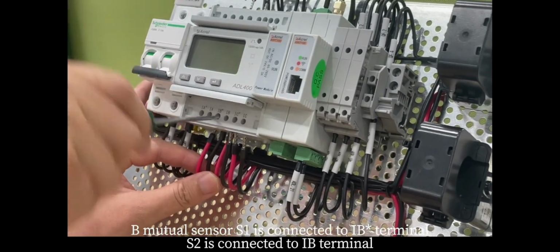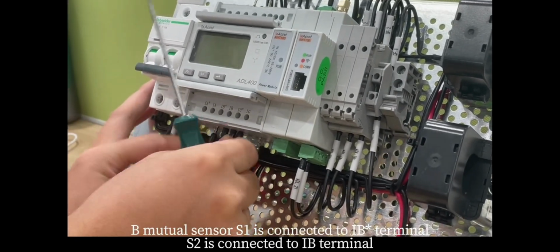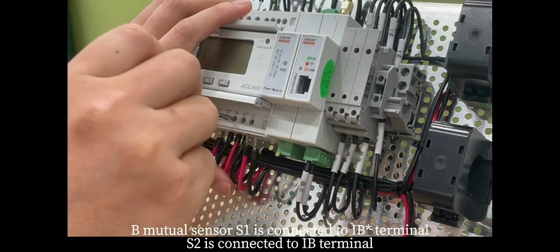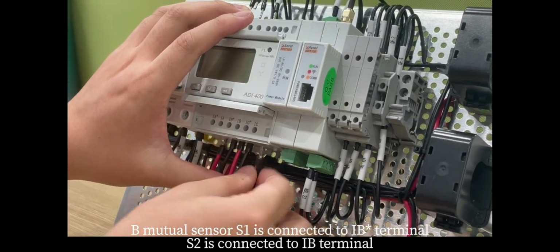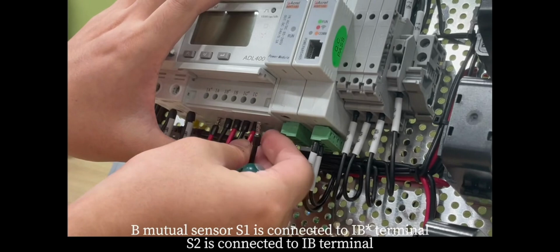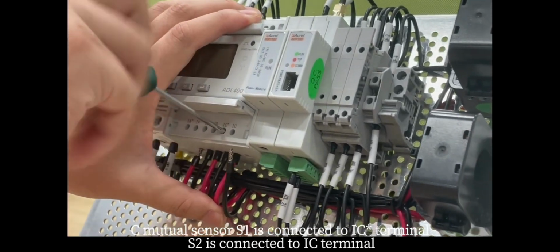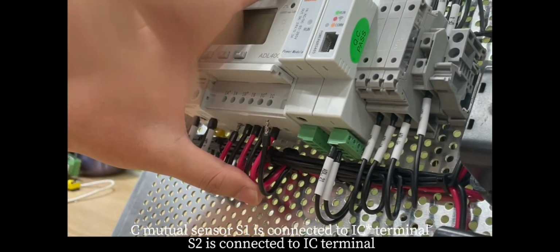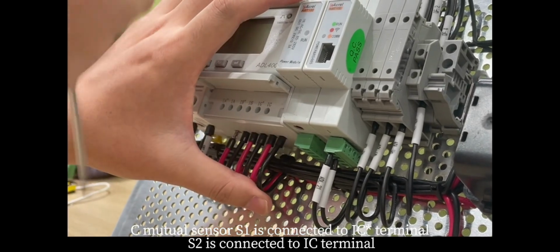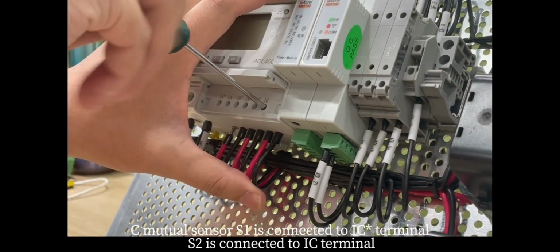B current sensor S1 is connected to the IB positive terminal, S2 is connected to the IB negative terminal. C current sensor S1 is connected to the IC positive terminal, S2 is connected to the IC negative terminal.